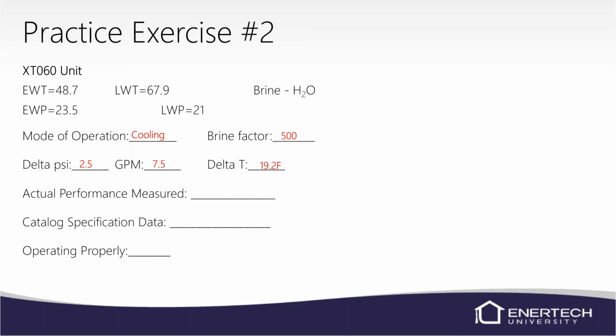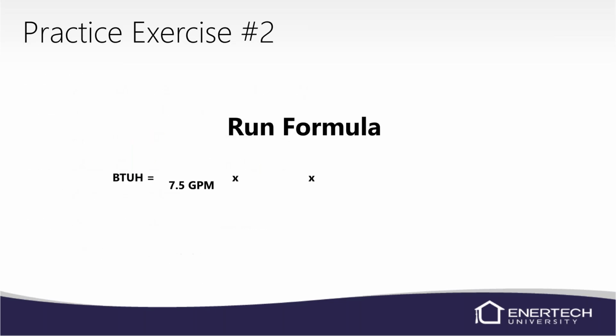Our delta T was 19.2. So now we have all the numbers that we need. We've got the manual in front of us. We can just run the math. So we run our GPM of 7.5 times our temperature difference of 19.2 times our 500 on our brine factor because we're not using antifreeze. So 7.5 times 19.2 times 500: 72,000 BTUs.